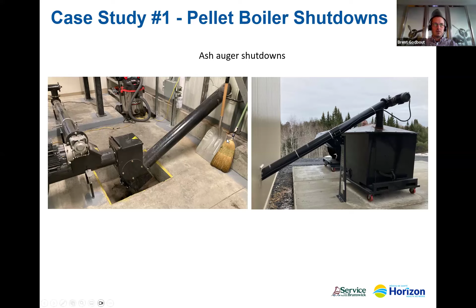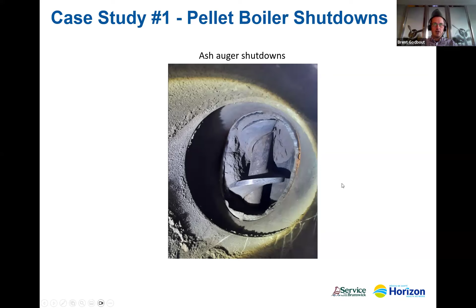This happened several times. Facilities guys up there are amazing, they come up with solutions to all this themselves. What was happening was we were getting condensation and moisture into those augers, and it was hardening all of the ash. So there's a picture of all the hardened ash, which was what was causing our motor to overload. They'd have to go in and chip out all this ash to get it going again.